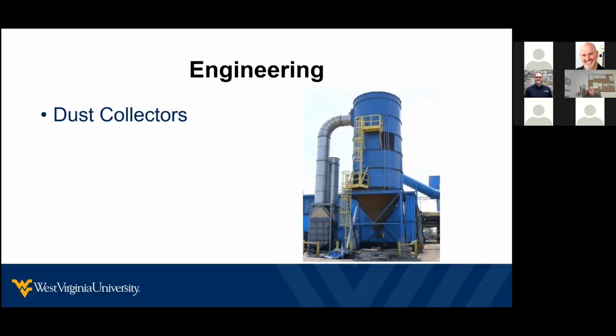Dust collectors. Use an appropriate dust extraction and collection system with the inlet located as close to the dust producing process as possible. Follow required standards and codes when installing these systems. Locate those dust collectors outdoors where possible. Do not use brooms or compressed air hoses to clean surfaces. Use only vacuums approved for dust collection. Use a dust extraction system that is designed to eliminate or control combustible dust.